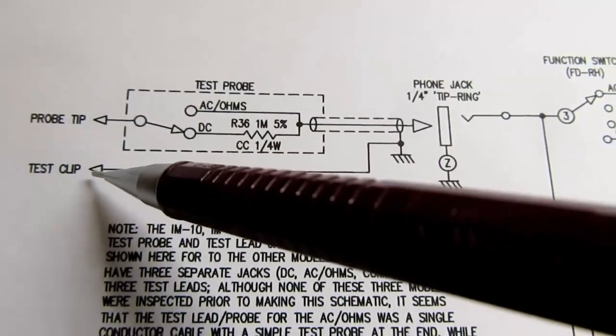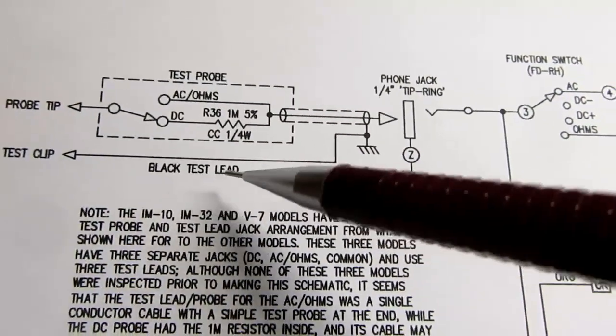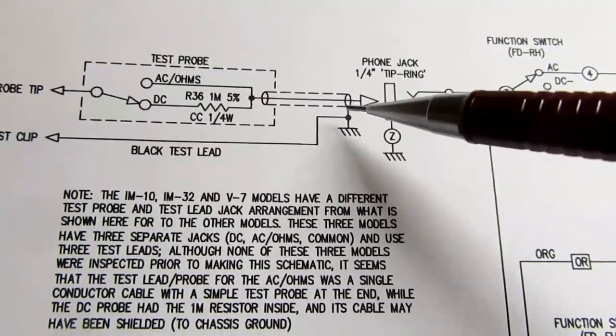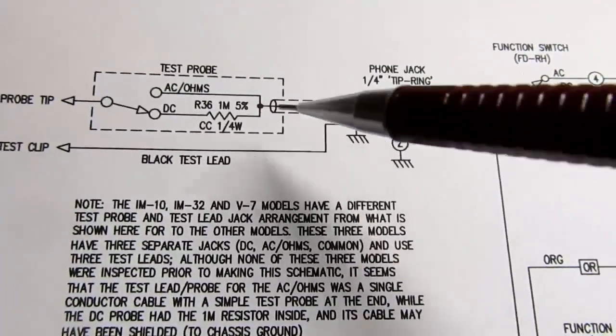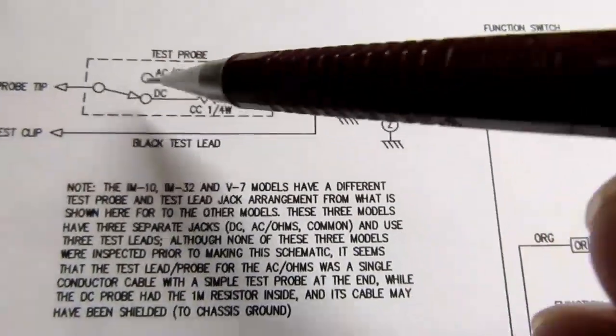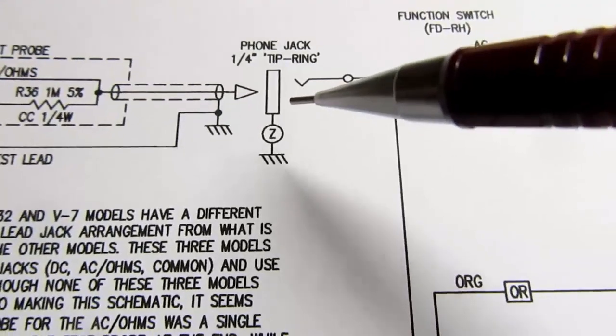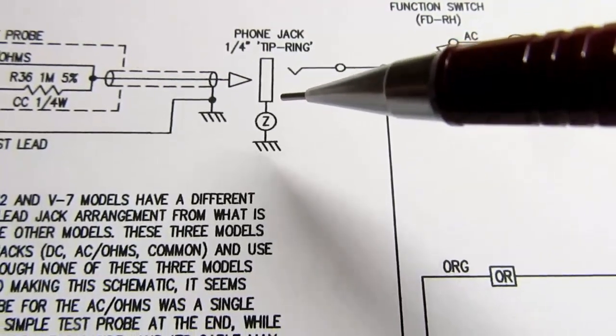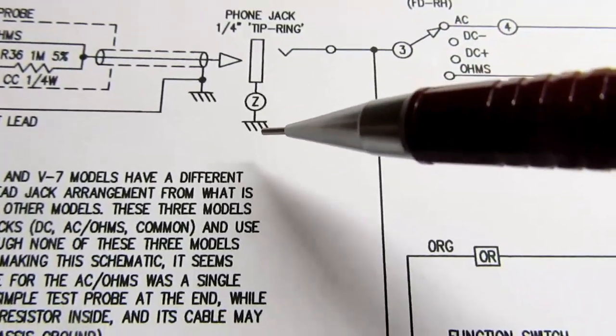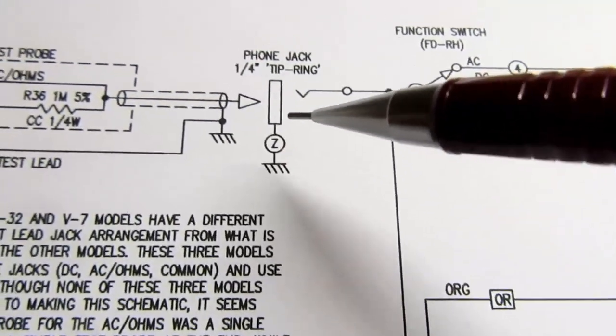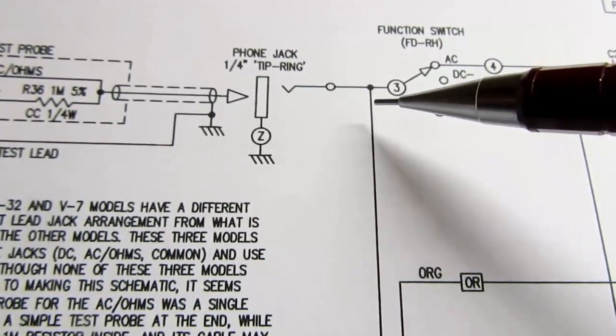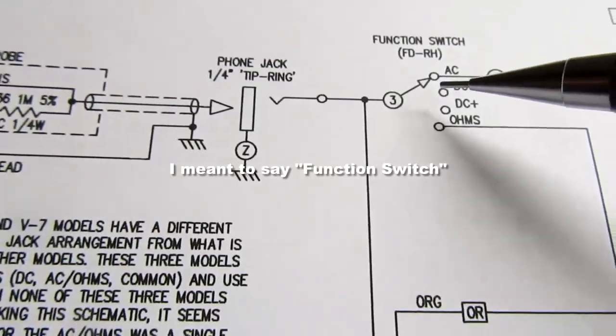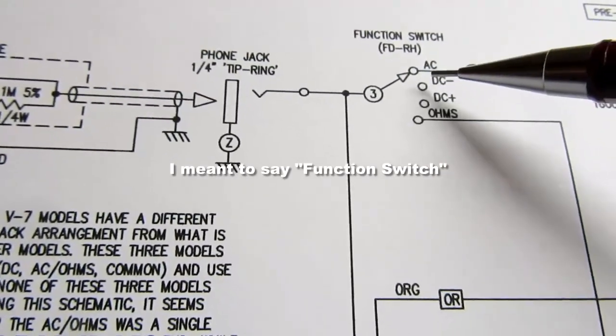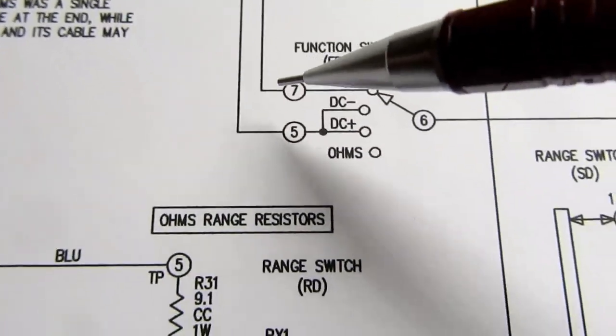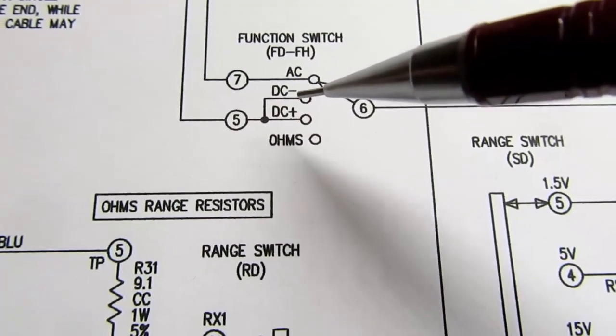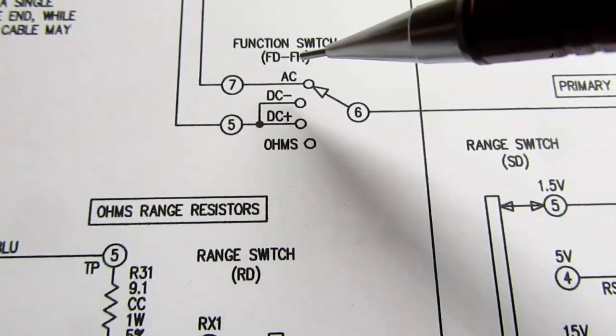And then the test clip for the common is just on a black wire that goes back to the ring of the phone type plug, and then the tip is coming from the probe tip. And then there is a 1/4 inch tip ring type phone jack with the ring tied to chassis / circuit ground, and the tip being connected here. There's the function switch here. This part of it's only engaged for AC volts, so let's follow it down here to another deck on the function switch. This is the front deck, front half.